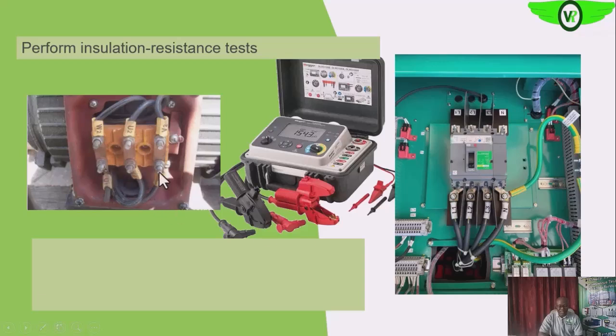We can disengage the star point, okay? This is a delta connection, but if it is starred, we can disengage the star point and then test the insulation between phases. But here we can only test the insulation between the winding and ground, okay? But in this case, once we disengage these shunting bars, we can test the insulation between the phases and between the phases and ground, as you will see in the video that the link is dropped in the description below.